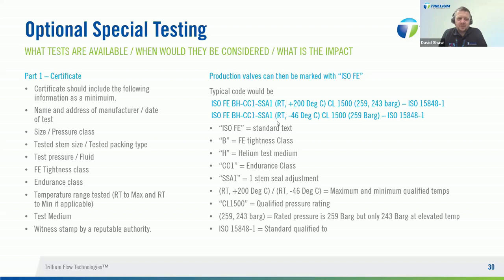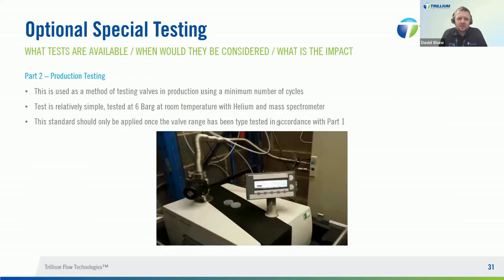Once you've done the prototype testing and are manufacturing valves to the prototype design, you can then do what's called a Part 2 production test or sniffer test. This is a much simpler test — you're testing the valve at 6 bar G using helium as the test gas and a mass spectrometer to detect any leakage. This type of test should only be conducted once the valve has already undergone a prototype test, and is just to ensure there are no issues with the manufacturing or assembly process.